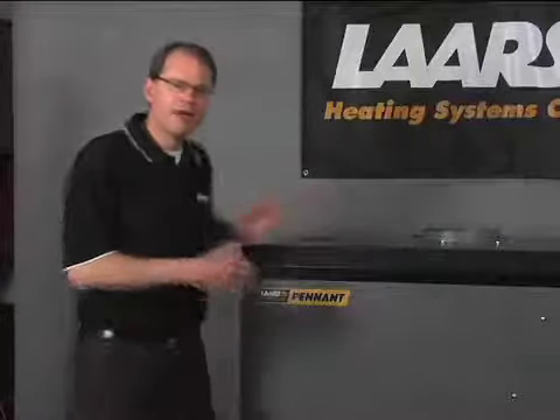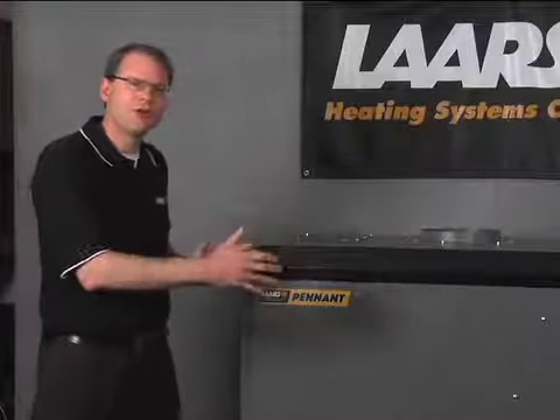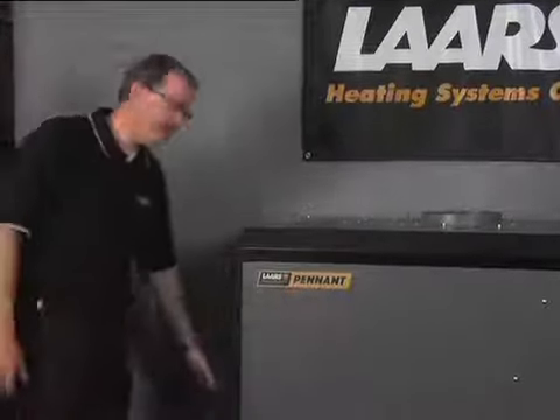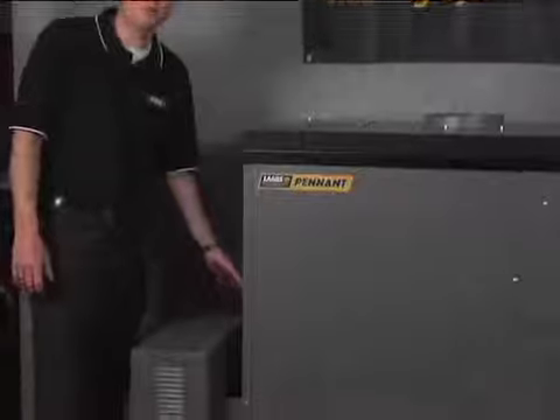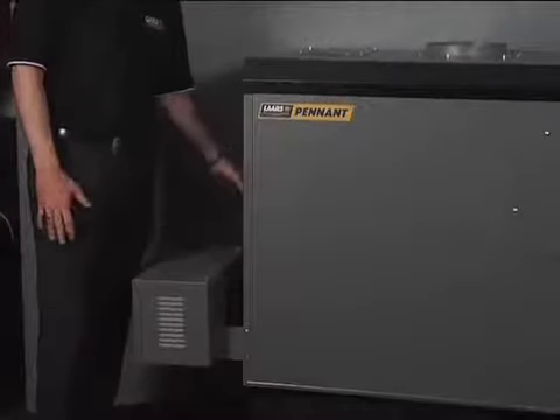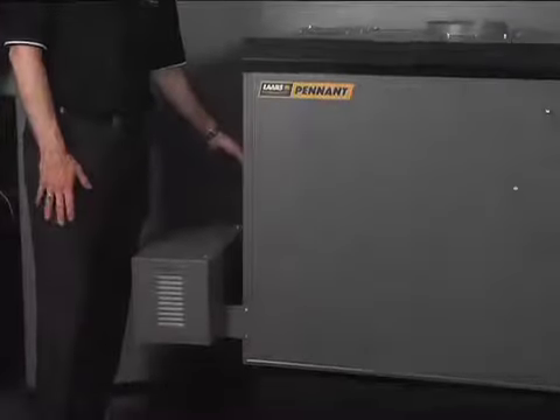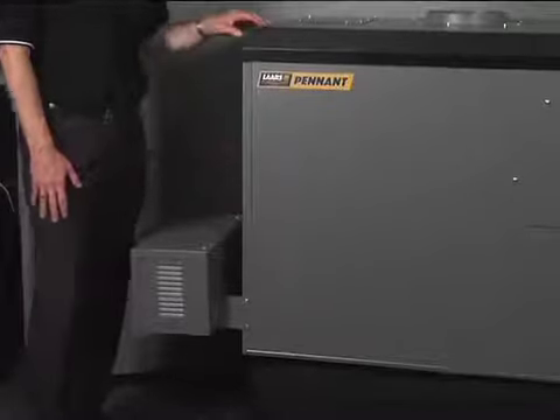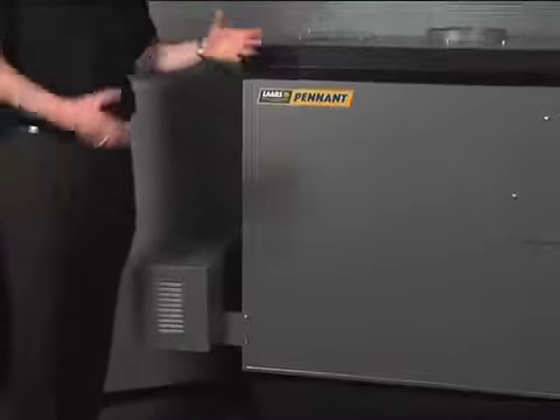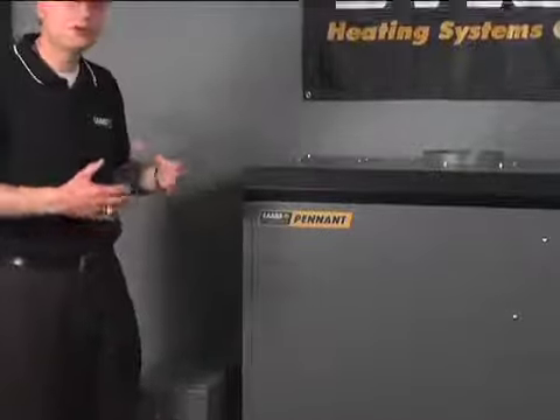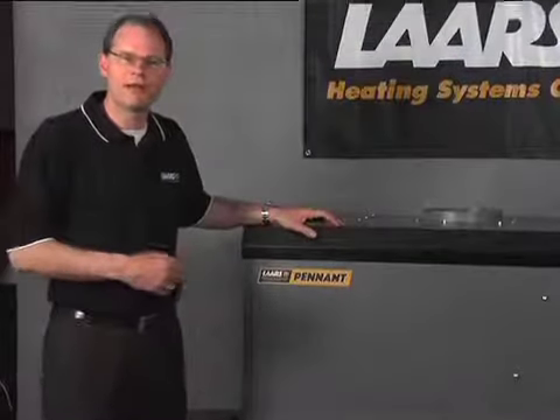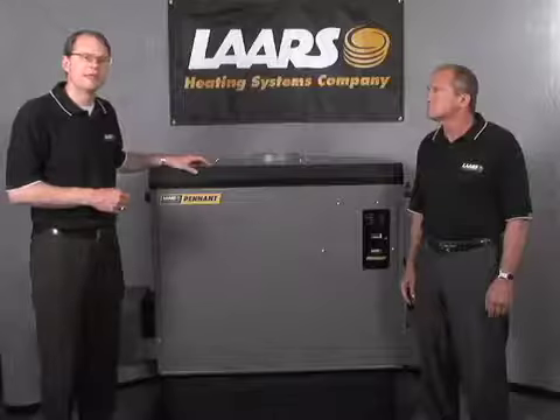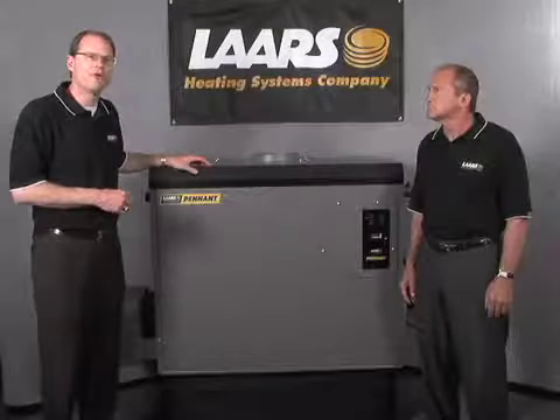Either with the copper fin tube or the copper nickel heat exchanger, Laars does have a proprietary pump volute which mounts on the heat exchanger. Quite a unique feature to Laars to have the boiler pump mounted right on the heat exchanger, and it includes with it suction guides to make sure that the flow to the pump impeller is correct, and that we get equal flow through the heat exchanger tubes on the boiler.